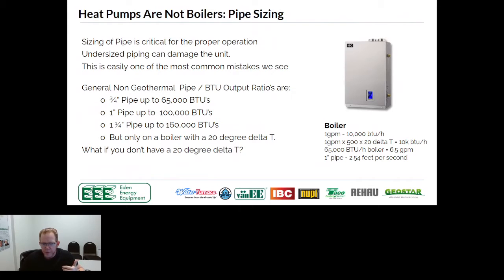So if we looked at it, for example, on a 20-degree delta T, if I had 6.5 gallons a minute and I needed to deliver 65,000 BTUs, which is just over 5 tons of capacity, in a boiler application I could get away with 1 inch pipe. It would be 2.54 feet per second, because if you look at the math on the right-hand side, if I'm doing a 20-degree delta T, assuming water, it's 6.5 gallons a minute.